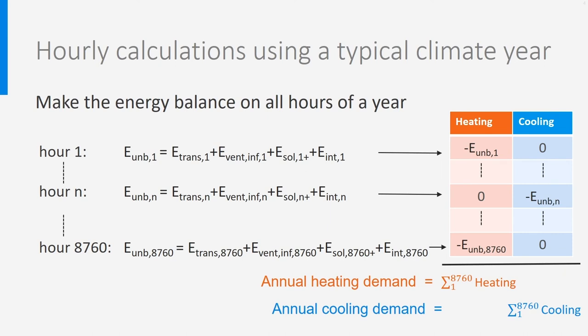Let's now take a closer look at the hourly calculations over one year. Let's start with hour 1 and make the energy balance. If the unbalance is negative, there will be heating needed during this hour; if the unbalance is positive, there will be cooling. We do the same for hour 2 and go further to hour n, and finally to hour 8760. We now know for each hour if there is heating or cooling. The only thing we need to do to get the yearly heating demand is to add all hourly heating demands, and for the annual cooling demand, we add all hourly cooling demands.